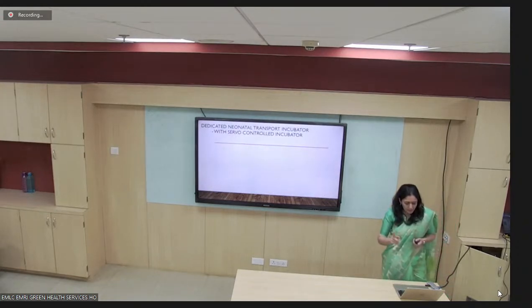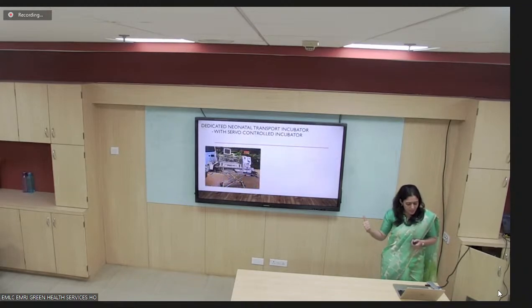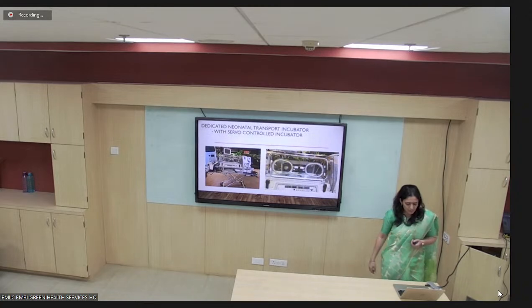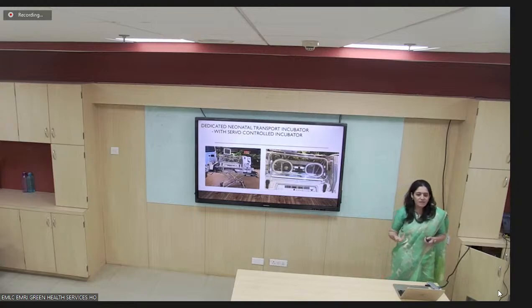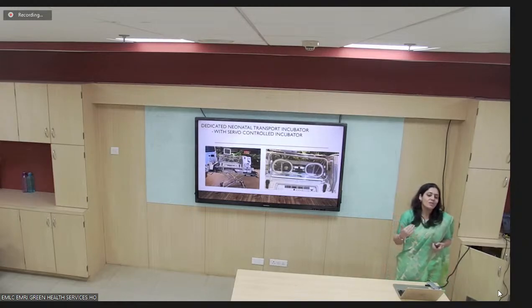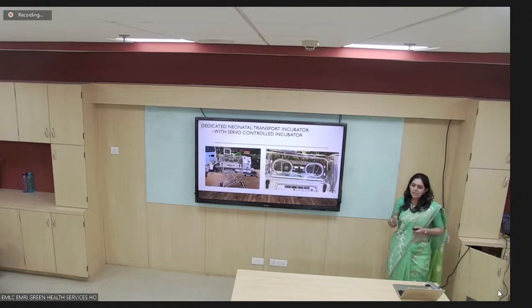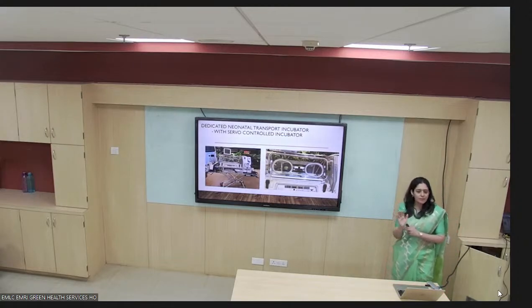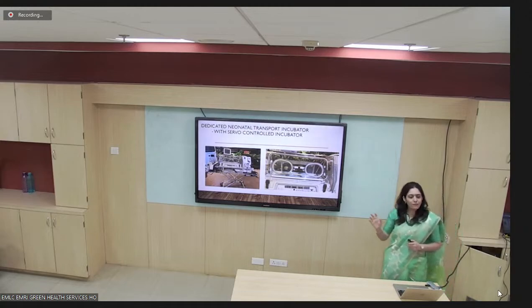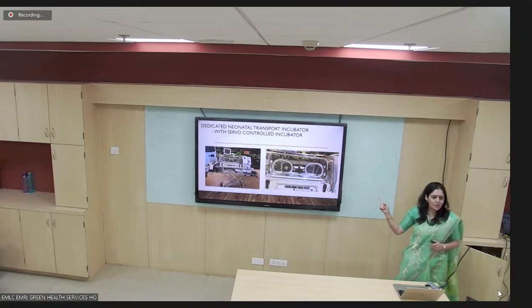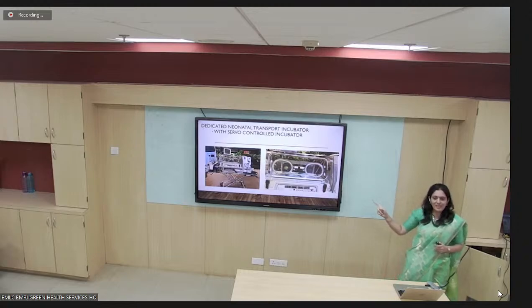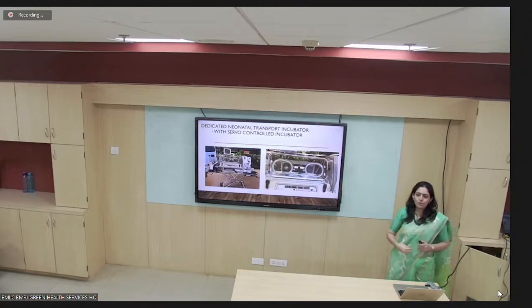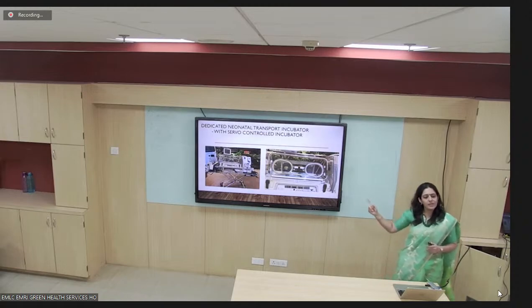So a dedicated neonatal transport incubator with servo control looks like this, which can fold and you can push it inside. This can be used for babies up to 4 kgs or 4.5 kgs, starting from babies as small as 350 grams whom we have transported. So from a hand-sized baby to a baby of 4.5 to a maximum of 5 kilos can be transported in this incubator. It is servo control. That means we just have to put a probe onto the baby's abdomen and that will automatically control the temperature.